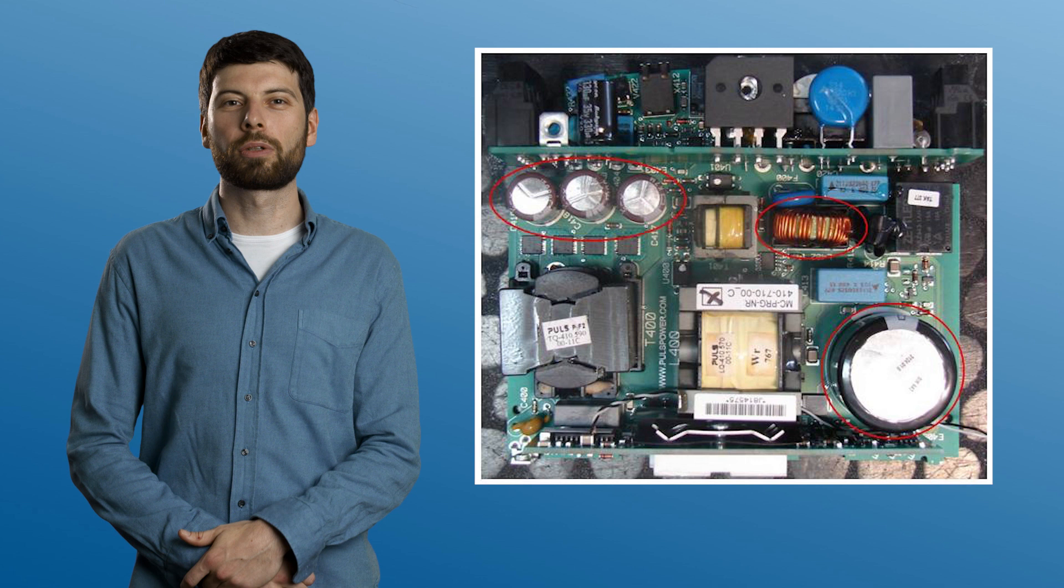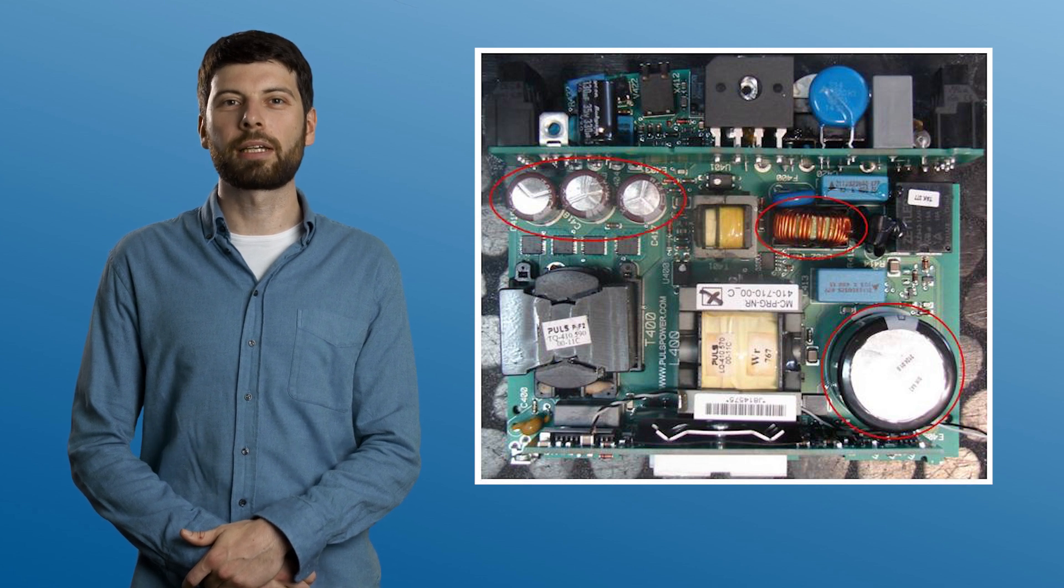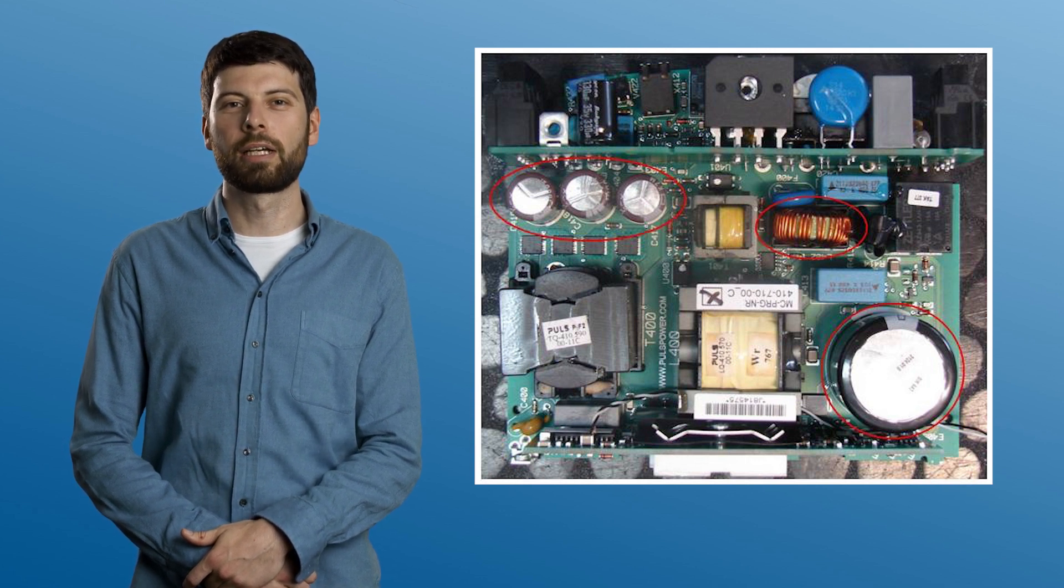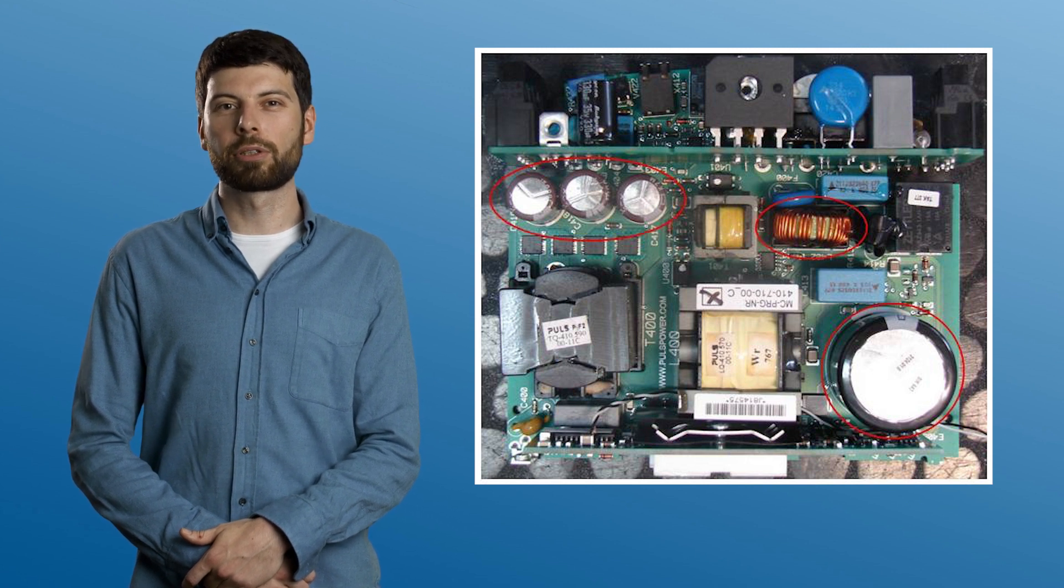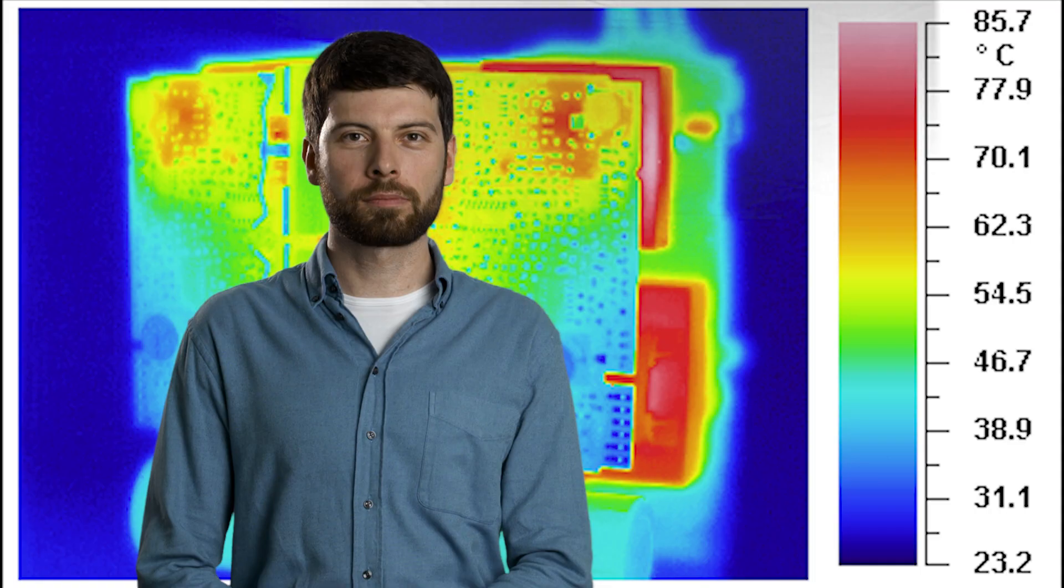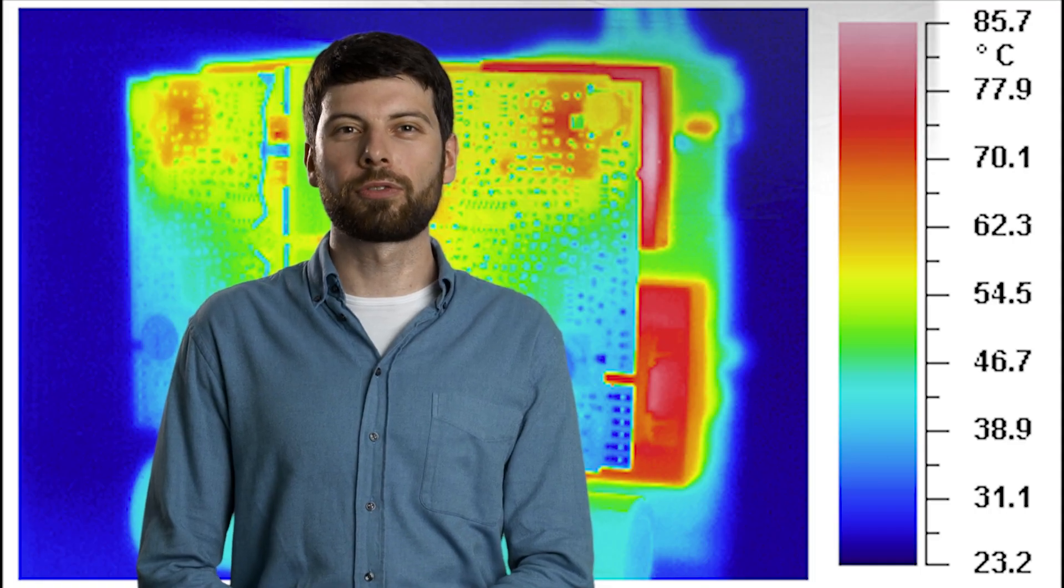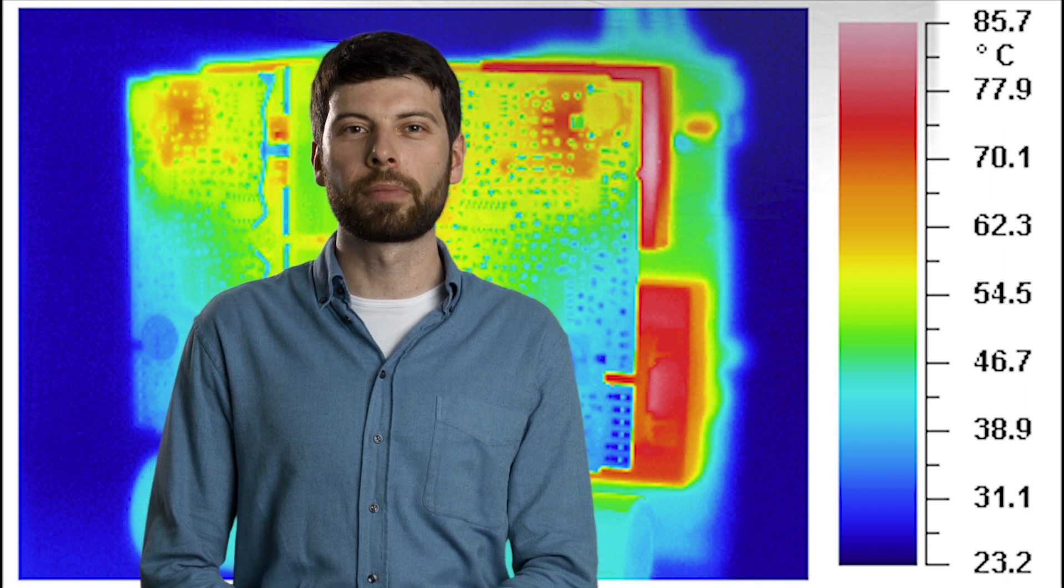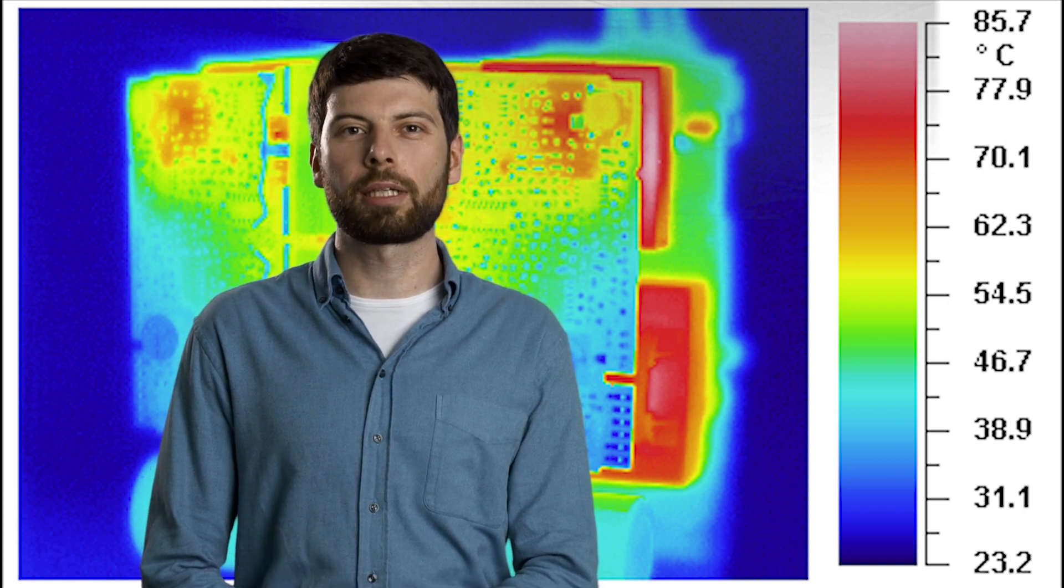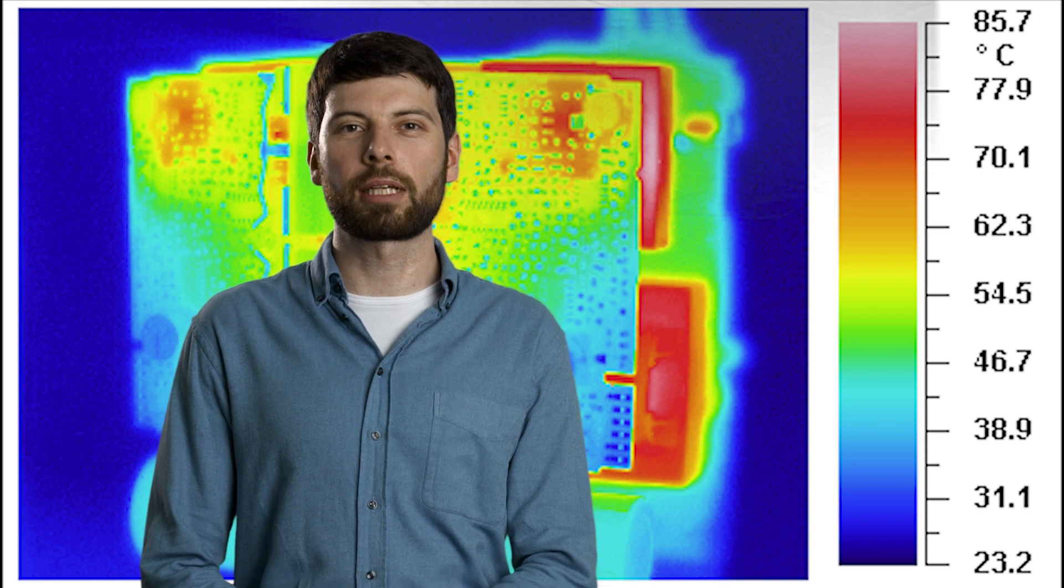Some components have limited service life, especially in the case of electrolytic capacitors which dry out over time. When the characteristics deteriorate the power supply fails. Just as with the failure rate, the product lifetime also follows the 10 degrees Celsius rule, which means lowering the temperature by 10 degrees Celsius doubles the lifetime.